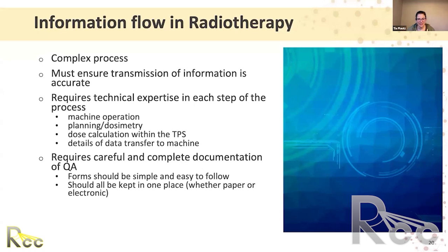One of my colleagues actually worked as a consultant in a clinic several years ago, and the physicist who had previously been at that clinic went out on medical leave somewhat urgently. And so she came in and took over the clinic and discovered when she did her calibration procedure that the machine had previously been calibrated and was running 8% hot. And normally our tolerance is about 2%. And so it was a bit alarming.